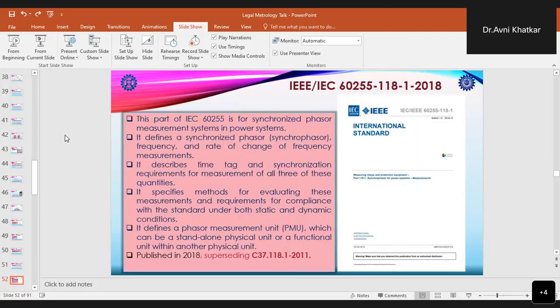Again, in 2018, a standard was published superseding the earlier 2011 standard. Now, this is the most current and the prevalent standard for the PMUs, and this is part of the IEC 60255 standard, and it is for the synchronized phasor measurement systems in the power system.